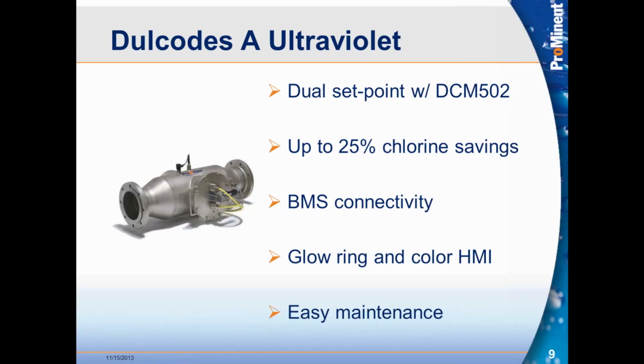The problem with running at a chloramine destruction dose, the higher dose, 24/7, is that you wind up destroying about 25% of the free chlorine in the water, as well as taking care of the desired combined chlorine, the chloramines. Optimally, talking back to the smart disinfection, the smart dosing principle is that our ultraviolet systems feature 2 set points, which can be controlled via the DCM 502 system. So we have a low dose set point and a high dose set point. And the DCM, depending on the combined chlorine reading, can tell the UV unit to run at the low dose or at the higher dosing level.